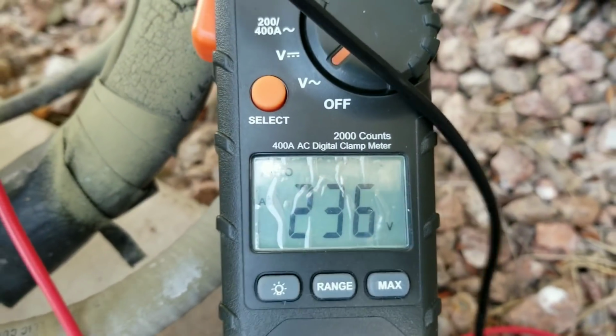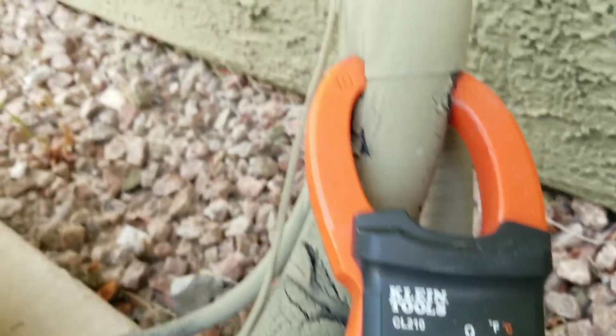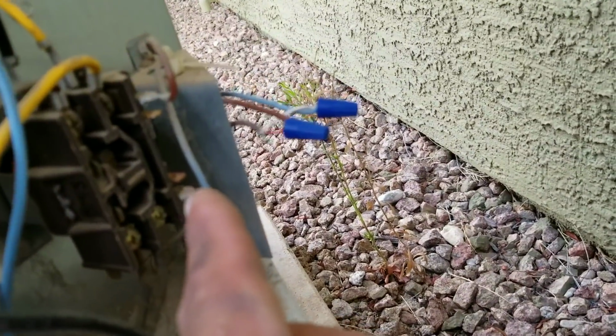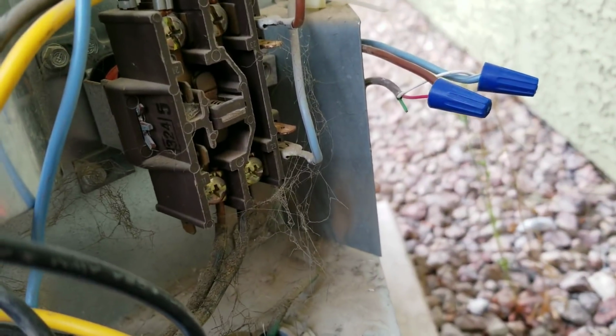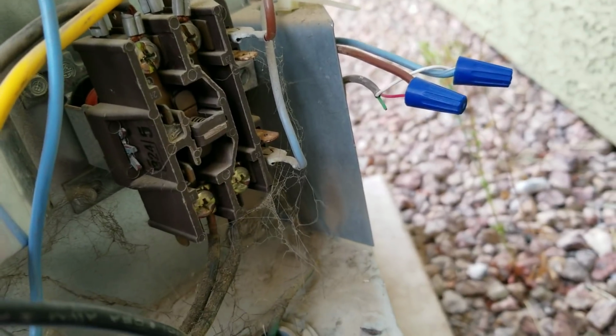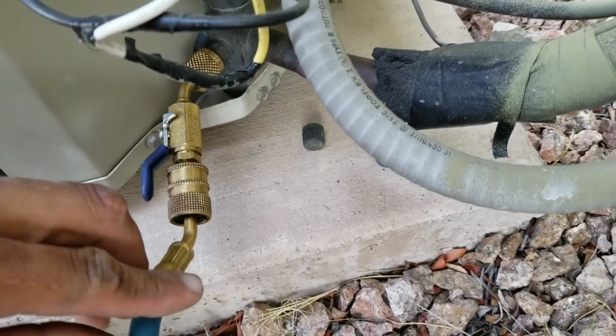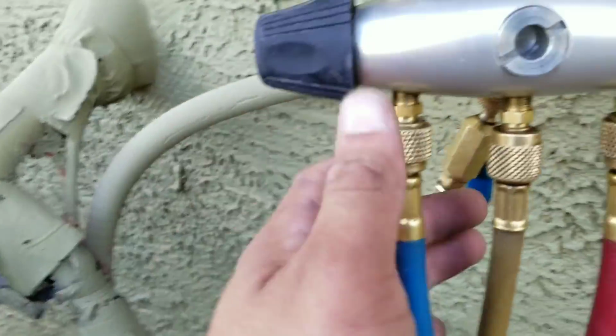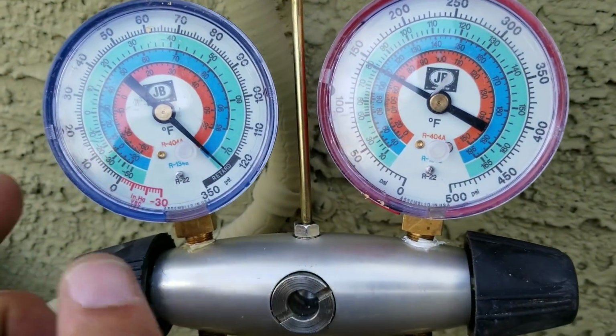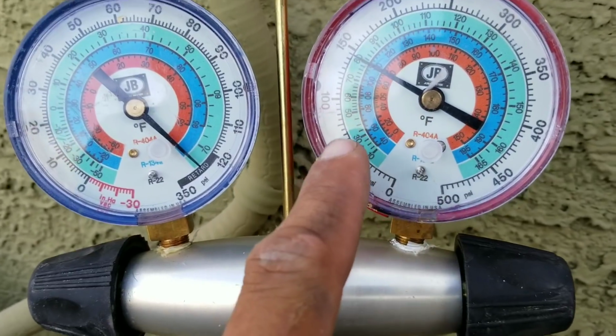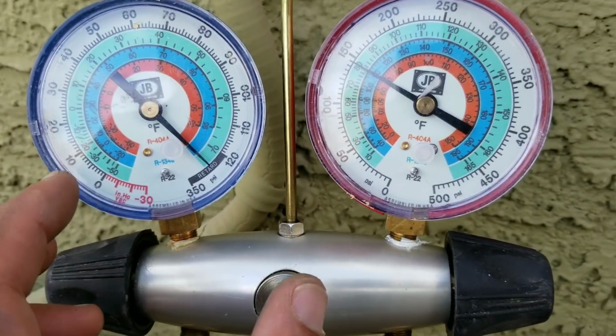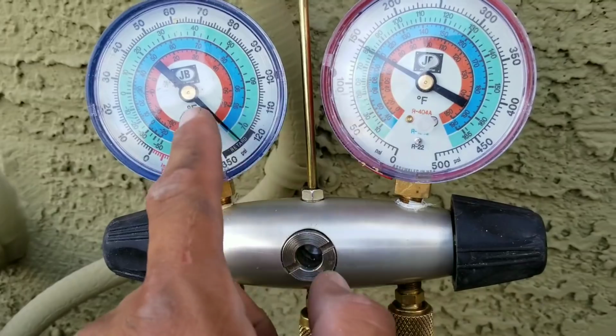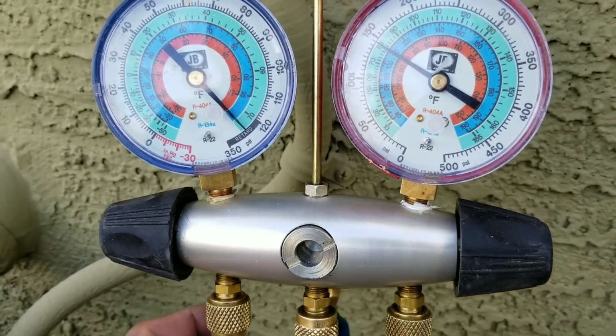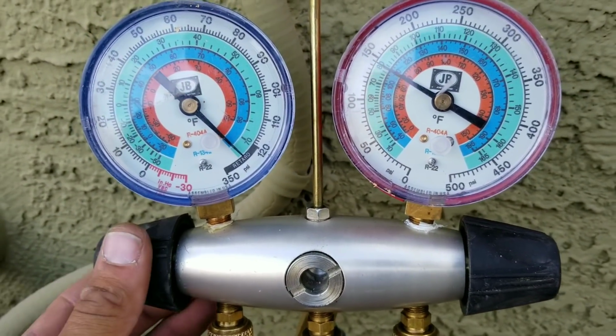So at this point I know, from doing my testing, that I do have a low voltage reading. I do have 240 volts coming in, 240 volts going back out to my compressor. Here I connected my gauges. This is my low and my high side. Pretty much I'm going to look at my meters, and my meters right now tell me that I do have refrigerant or pressure inside of the compressor. It's in the retard position. That just simply tells me that I do have refrigerant, but the compressor is not running.